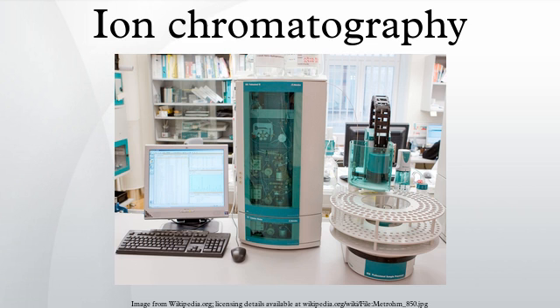A sample is introduced either manually or with an auto-sampler into a sample loop of known volume. A buffered aqueous solution known as the mobile phase carries the sample from the loop onto a column that contains some form of stationary phase material. This is typically a resin or gel matrix consisting of agarose or cellulose beads with covalently bonded charged functional groups.